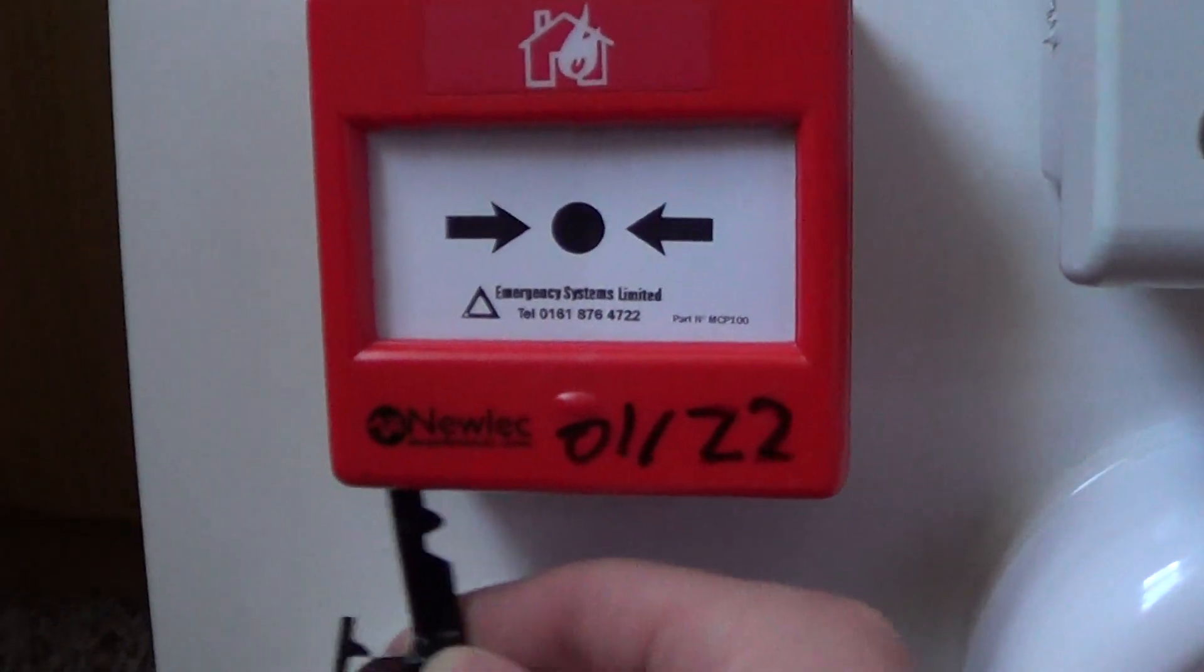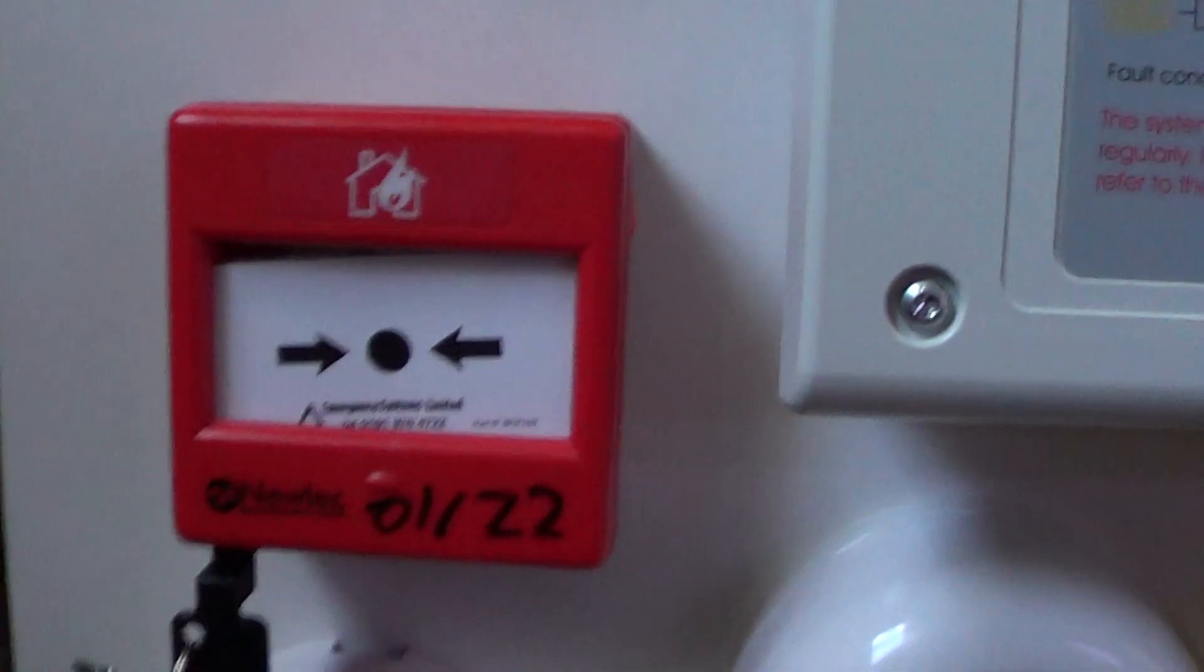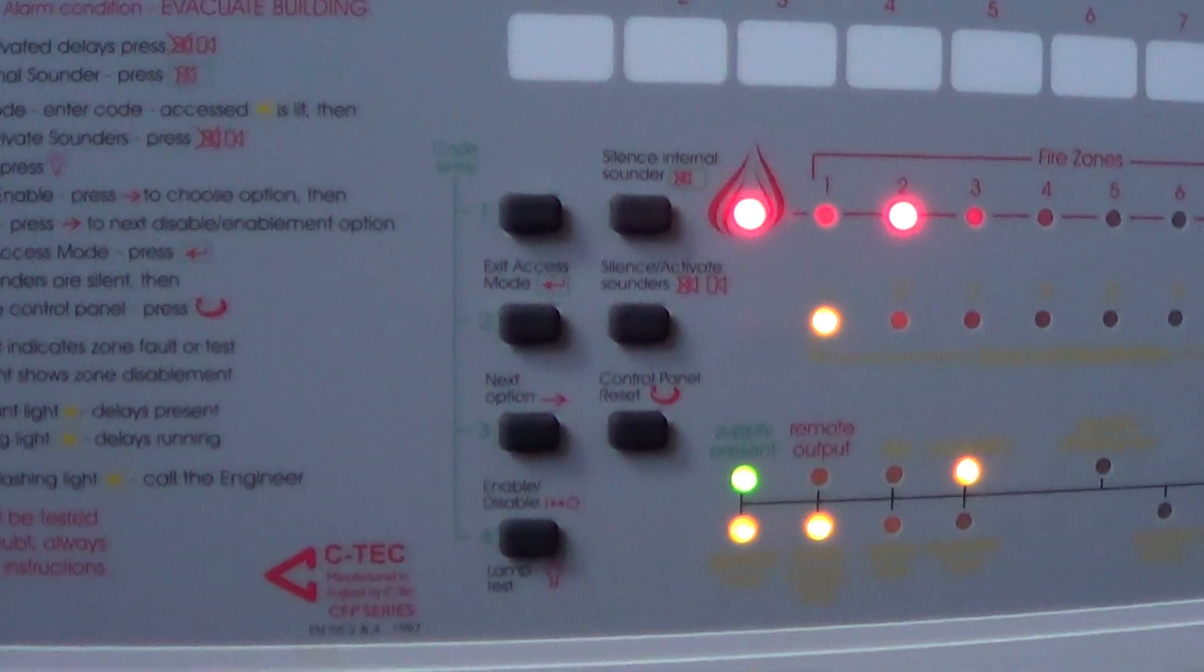Now I'm going to test zone two. I'll first start off with this one. This call point has glass in it and I'm not going to break that. The key's down. I'll just pull the key out to make sure it doesn't go off again. Reset the panel now.